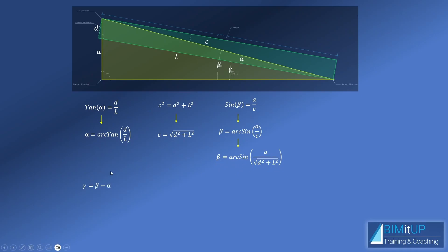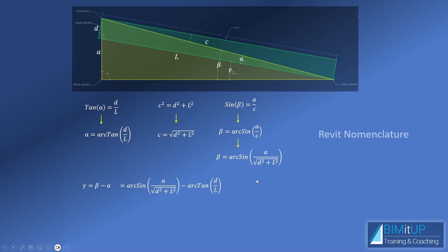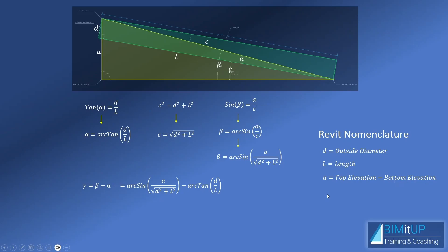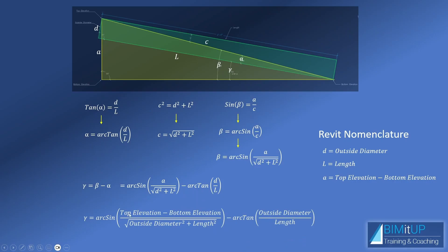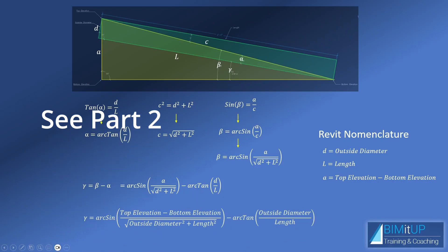So finally, we know that gamma, this angle here, is the large angle beta minus the small angle alpha. But we already know beta is this expression here and alpha is this expression here. So if we plug it in, this is what we obtain. And then now we just need to take it to Revit nomenclature, which is we know D is the outside diameter of the pipe. L is the length of the pipe. We know that top elevation of the pipe is this name. Bottom elevation of the pipe is this name. So that would be A right here. So we end up with this expression. And then this is the formula that we're going to use in Revit. So let's jump into Revit.